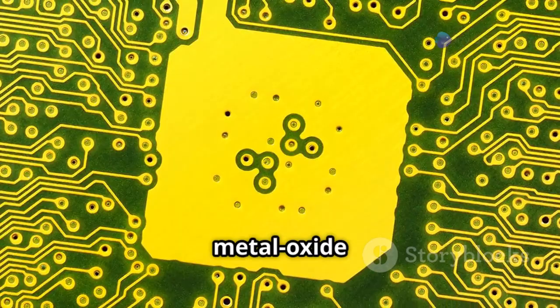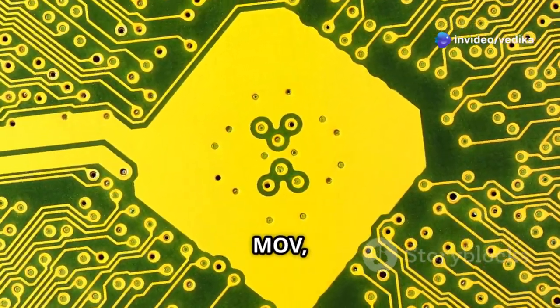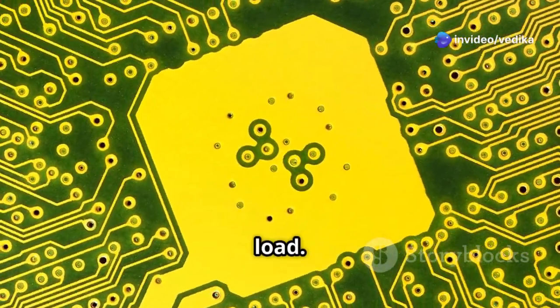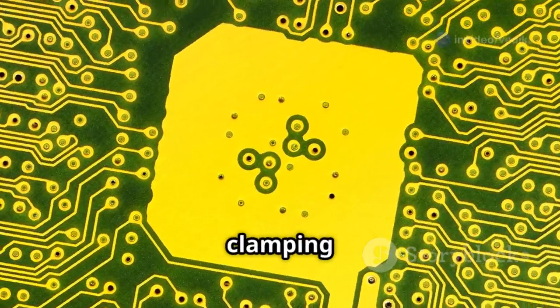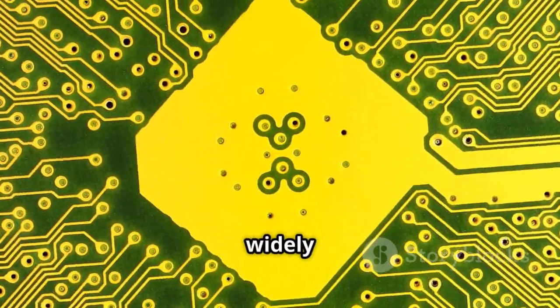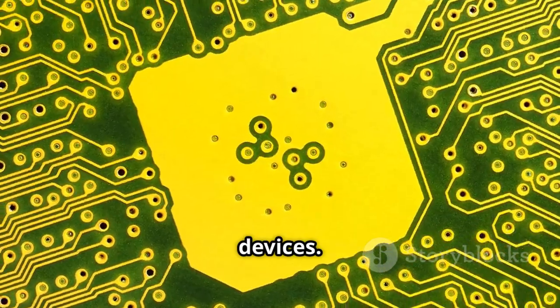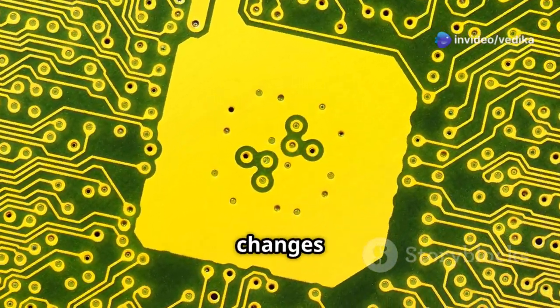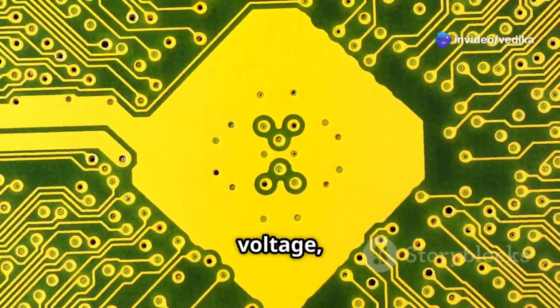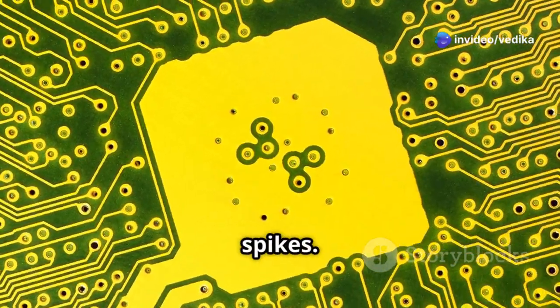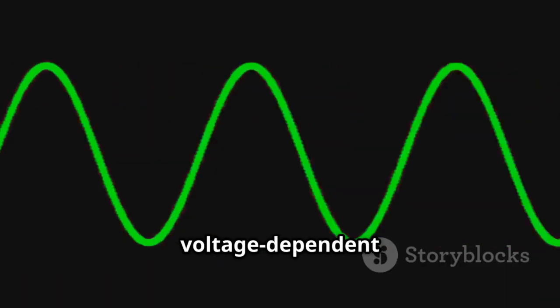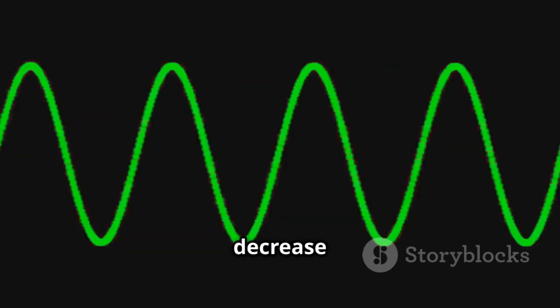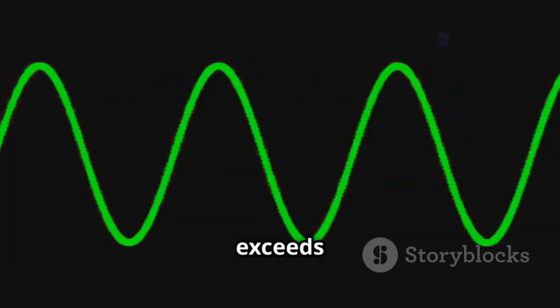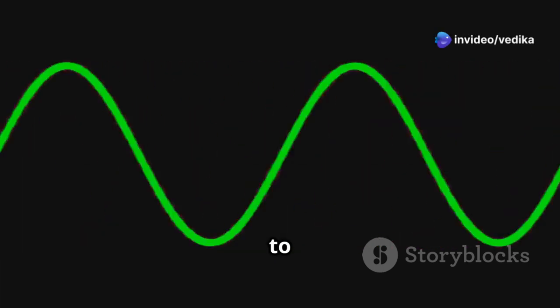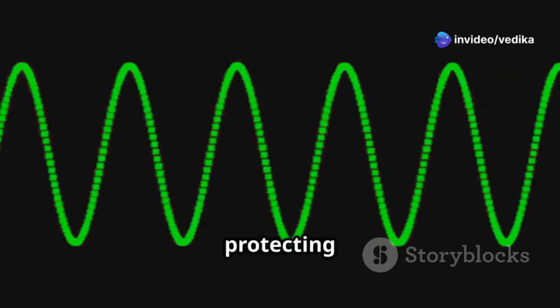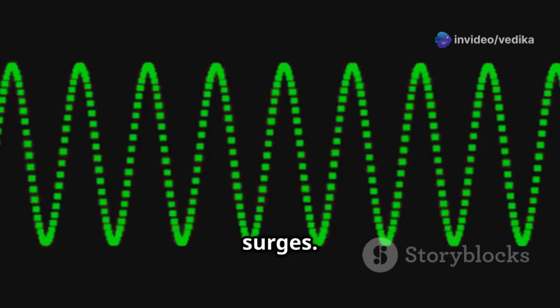Another option is to use a metal oxide varistor, or MOV, in parallel with the inductive load. MOVs are particularly effective in clamping high-voltage transients and are widely used in surge protection devices. They are made from a ceramic material that changes its resistance with the applied voltage, providing a dynamic response to voltage spikes. MOVs are voltage-dependent resistors that exhibit a sharp decrease in resistance when the voltage across them exceeds a certain threshold. This allows them to clamp voltage spikes effectively, protecting the circuit from potentially damaging surges.